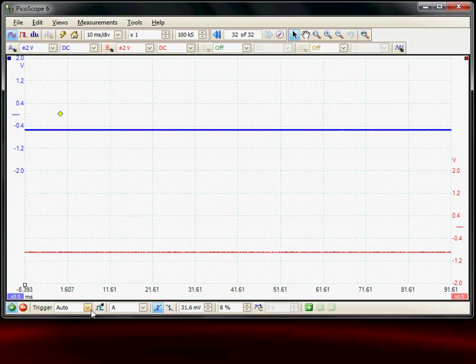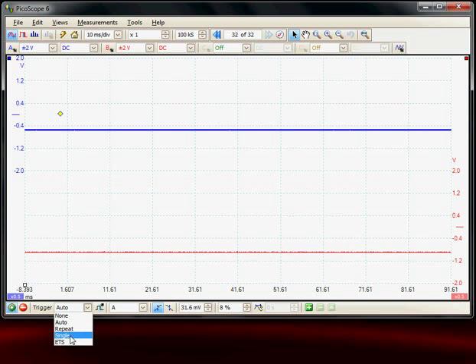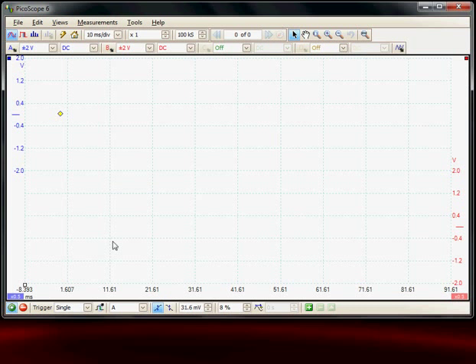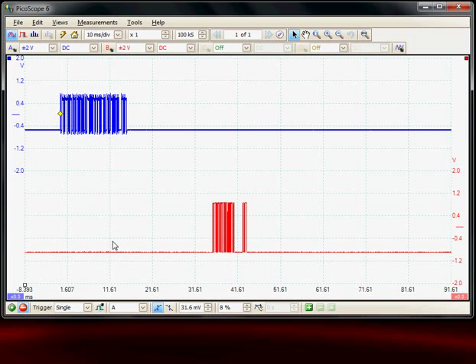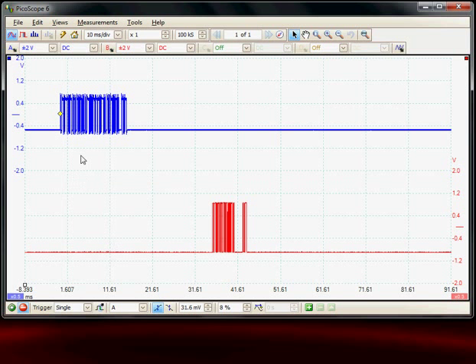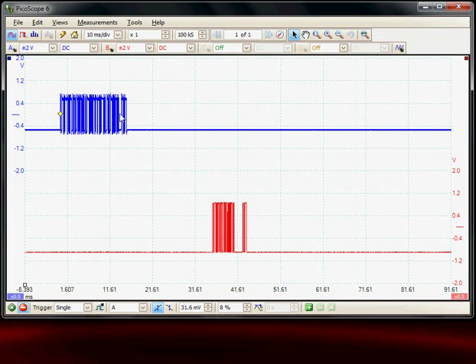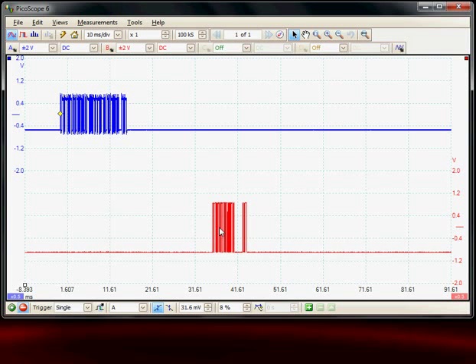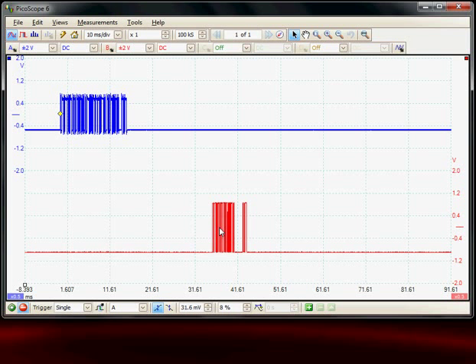I'm going to change the trigger condition to single trigger and then arm the trigger condition. This is now waiting for some data to be transmitted. Now we see some transmitted data. On channel A we have the trigger and acquired a transmitted burst of data, and then sometime later on channel B a received data packet appeared.